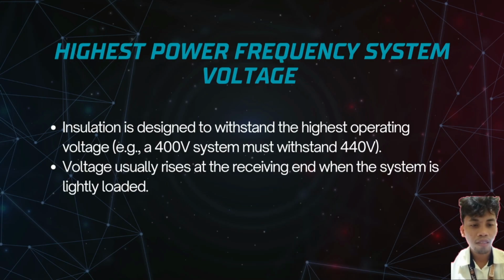So for example, kung ang usa ka system is rated 400 volts, ang iyang insulation nga kinahanglan makaya hangtod for 440 volts. So i-design kini para dili dali mo boto or masunog nga wire kung naay gamay nga pagsakang voltahe. Engineers don't design insulation just for the nominal voltage. They use a safety factor. If a system is rated for 400 volts, the insulation on wires in a transformer must be robust enough to handle the maximum expected voltage, so often 110 percent of nominal, without breaking down and causing a short circuit.